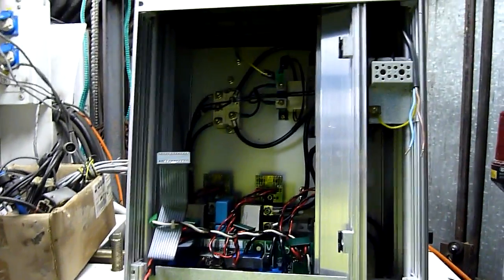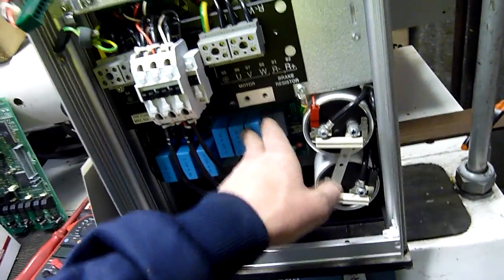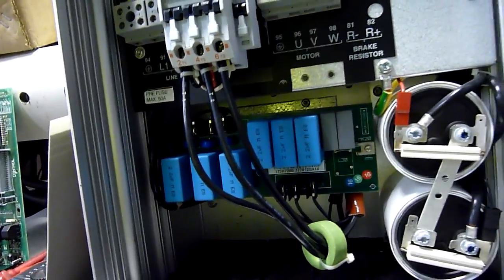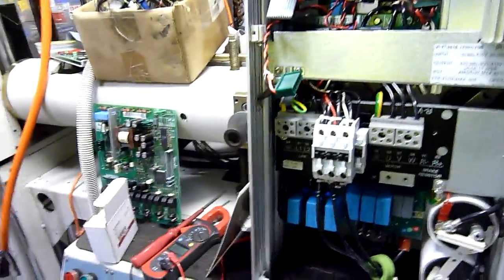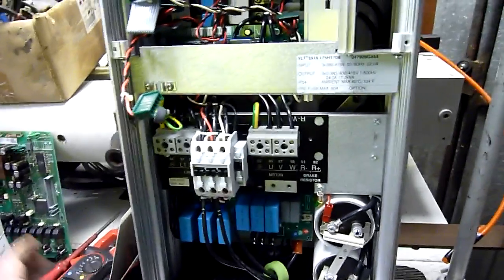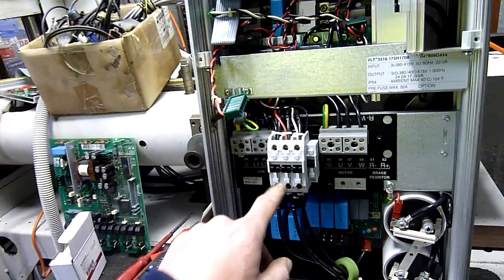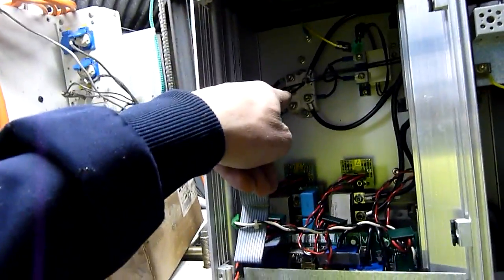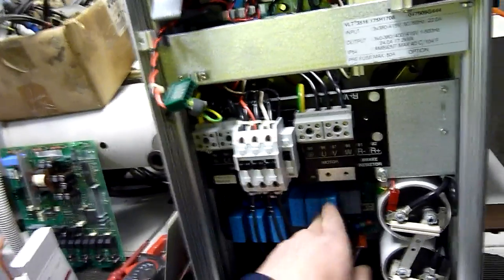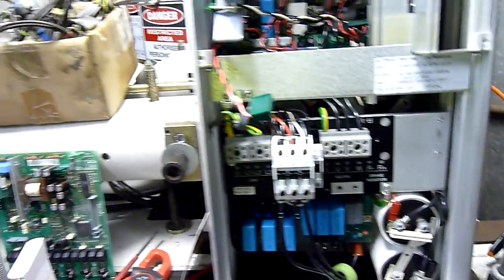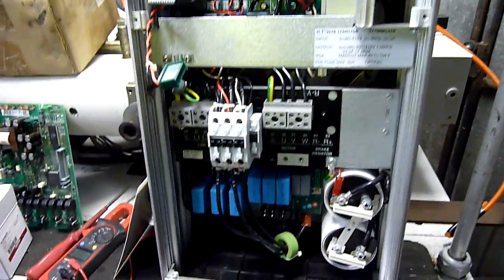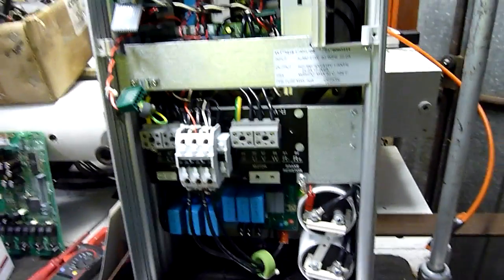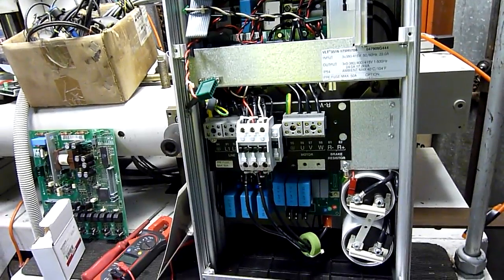But anyway as you can see I've got a big VLT drive here I've been playing with. I'm pretty sure it's this board here that puts a small amount of AC current to ground. Apparently it's a characteristic of some of the bigger and older drives and that takes out the RCD as well. So that's one of my other annoyances. Everything's fine until the RPC comes up. It detects three phases and goes to engage the contactor. As soon as three phases are generated, I think it's this that's sending it to the ground. It's got metal oxide varistors and a lot of these polyfilm caps. I was talking to Terry about it and we've canned a drive about quarter the size of this because it was just routinely or occasionally taking out the RCD. It's just a common thing with those old drives.